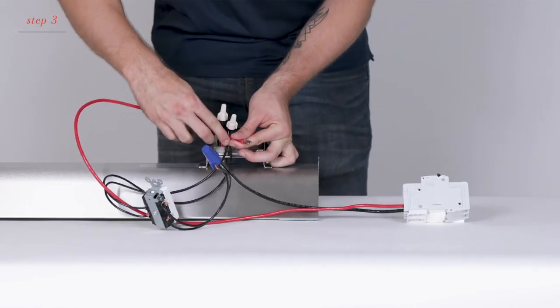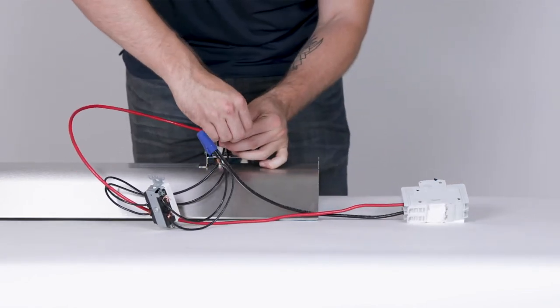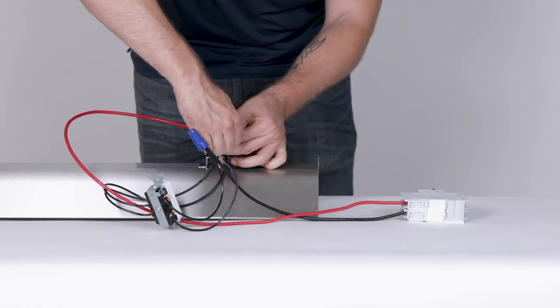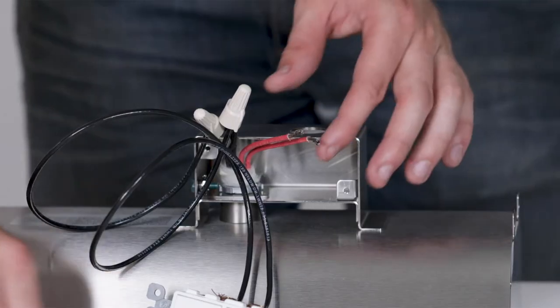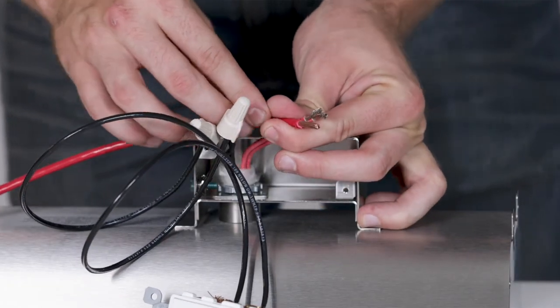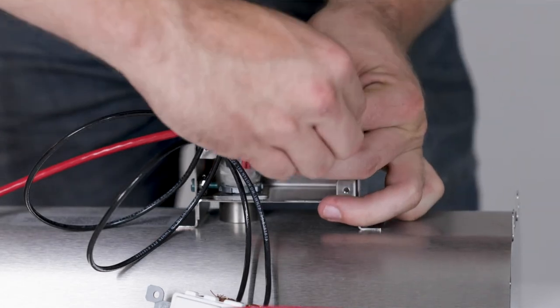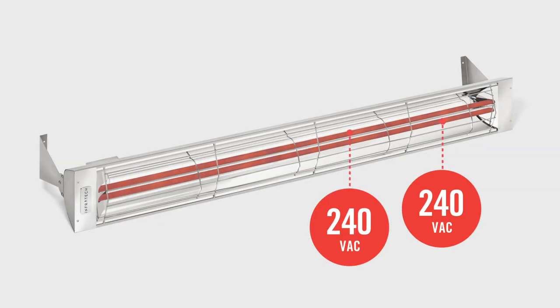Now, line 2 of the circuit goes directly to the heaters. You will terminate line 2 on the two red wires in the heater or the high temperature flex whip depending on how you are mounting the heater. After you connect your ground to the heater, the installation is complete.